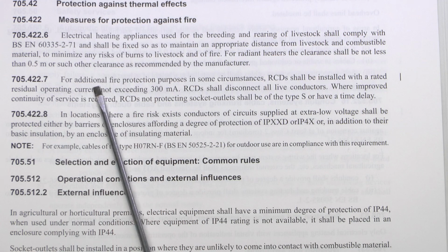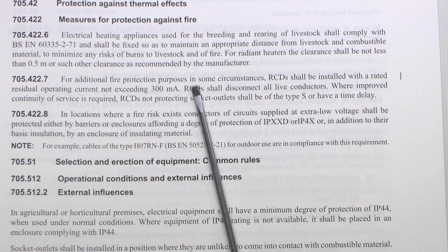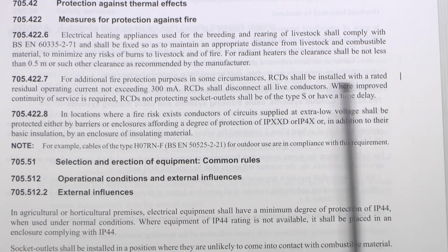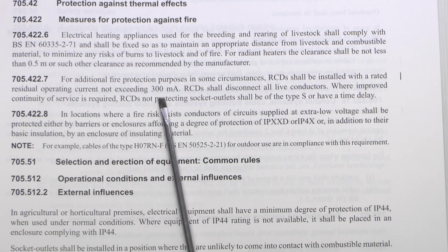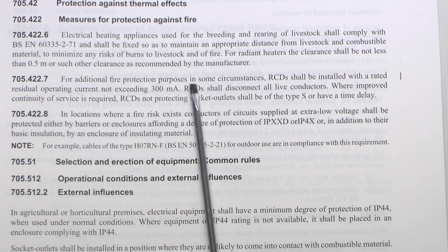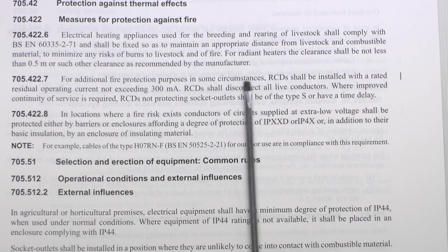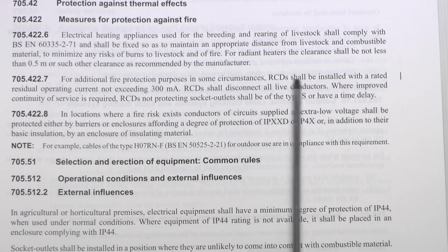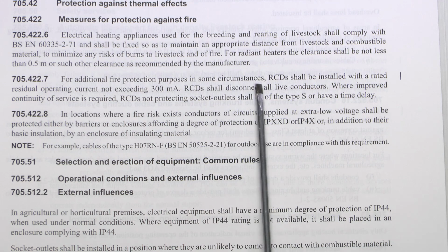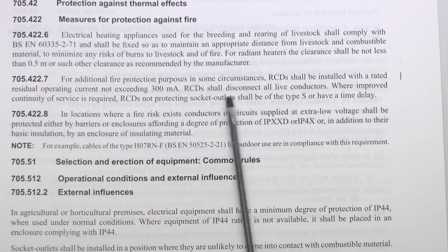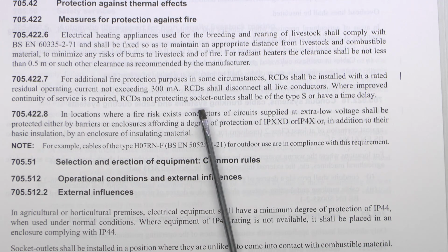And as we've got here, for additional fire protection purposes in some circumstances, RCDs shall be installed with a rated operating current not exceeding 300 milliamps. The additional part here is the wording "in some circumstances", whereas previously it was just that they would be installed, but now it is in some circumstances only, so not necessarily required in all situations.